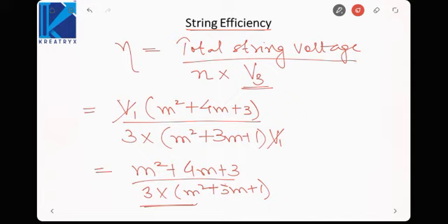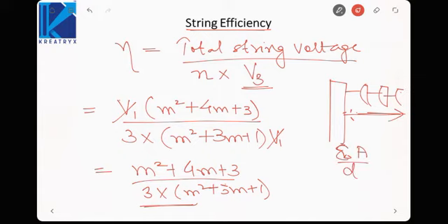Okay. Now what happens in case of strain type insulator? As we saw, there the discs were laid horizontally. And in case of horizontal, as you use more discs, the disc which is at the last will have the highest distance from the tower. And as the distance from the tower increases, the capacitance reduces.